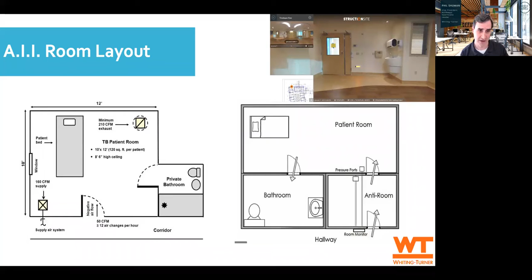So after looking at the codes and our understanding of AII rooms, what does that tell us? First, converting rooms is not a simple matter of rebalancing. In addition to meeting the architectural requirements, a larger impact to the facility's infrastructure should be reviewed. Especially as the number of rooms is increased, the demand on our existing systems is going to increase. Second, temporary AII rooms are not really addressed in the guidelines. If there are going to be some requirements that are adjusted, any adjustment that comes out will have to go hand in hand with education of our healthcare providers to distinguish what mode the room is in. You also need to look at the utility operating expenses. Slide, please.